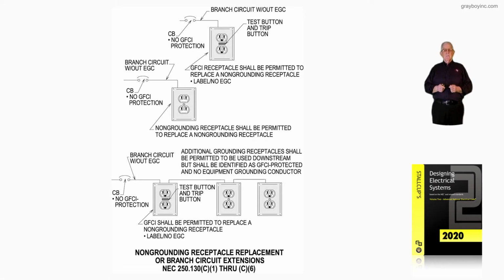Now, this illustration deals with non-grounding receptacle replacements or branch circuit extensions. Again, we're in accordance with 250.130(C)(1) through (C)(6), but notice here we're using a GFCI for replacement, or it could even be for extension. But notice at the very top of the illustration, we're using a circuit breaker, no GFCI protection, but we're replacing that receptacle with a GFCI.